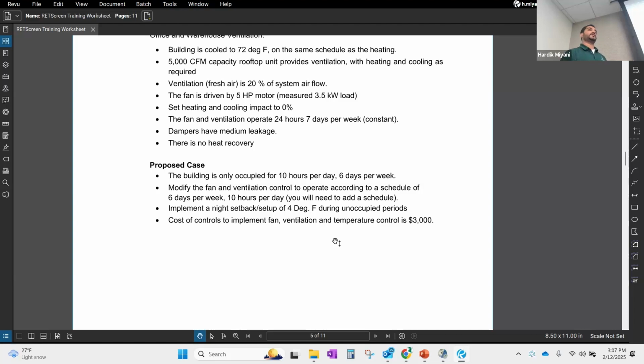Sometimes it could be 1.5 hours early that it needs to start. Sometimes it could be 30 minutes. Sometimes it could be 3 hours as well. So depending upon what the difference is, you are saving energy. Instead of having a fixed start at 5 a.m. all the time, now you are saving depending upon the ambient temperature and the load in the building, right? So that is what we are implementing here.